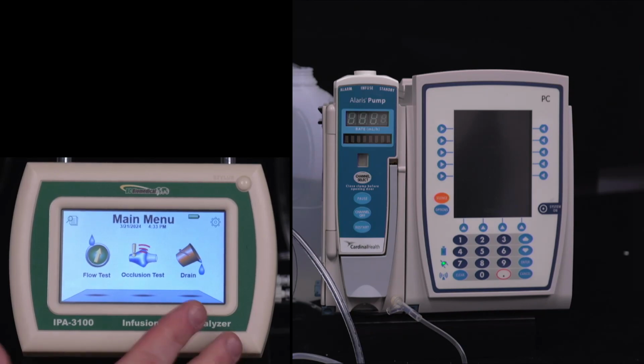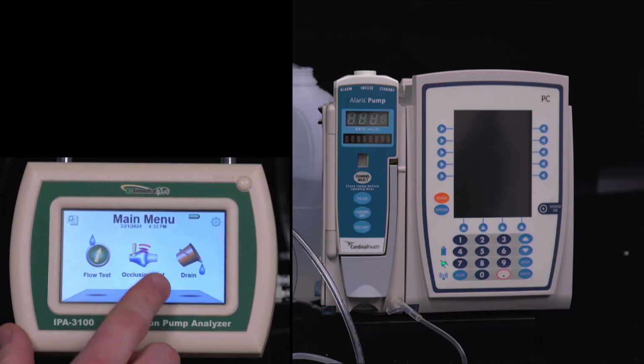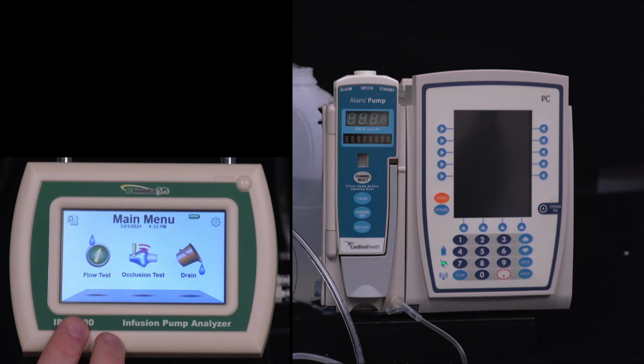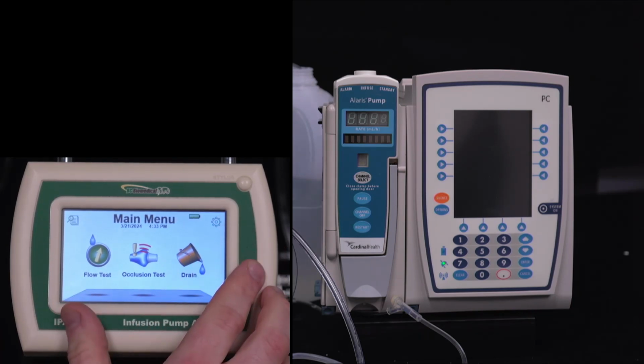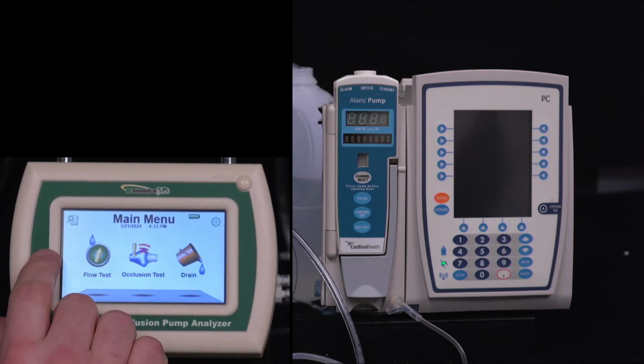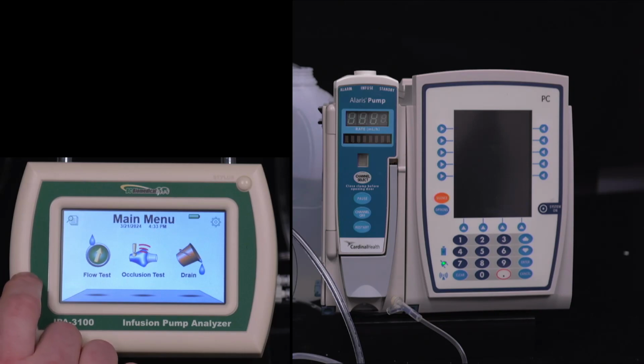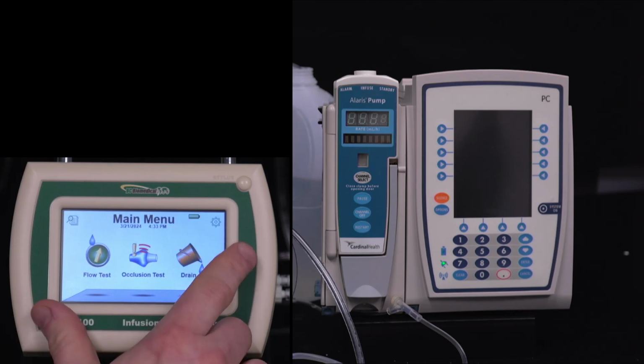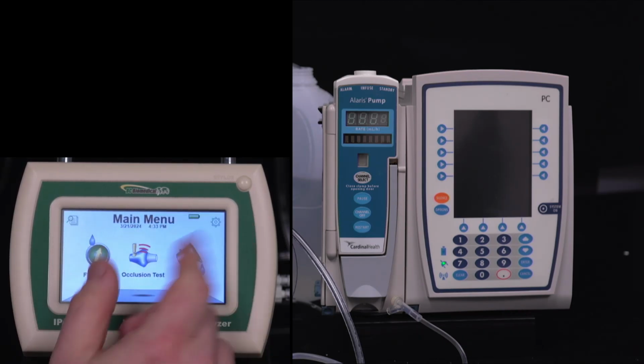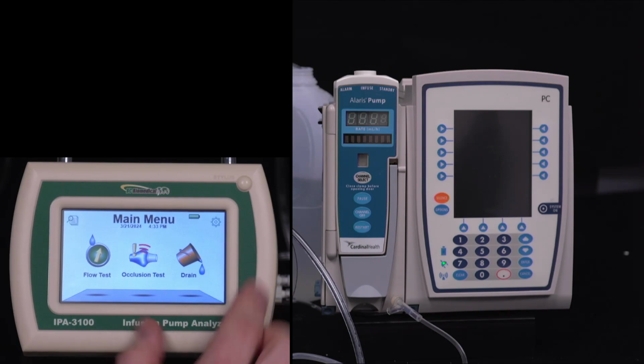Now this is the main screen that it powers up on, so it's very easy to perform the flow and occlusion testing and also drain the unit. Now we would drain it before we ship it or send it in for service. We want to make sure there's no residual fluid inside so it doesn't freeze or anything when we ship it. So we get a very easy interface from the main screen. We can view our test records from the top left here. We have a battery status indicator at the top showing us our battery level or whether it's charging if it's plugged in. We're currently running from battery.